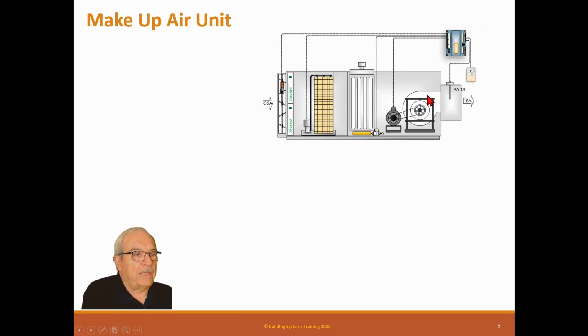Now this is a simple makeup air unit. This would be used for a kitchen or any other space where you have a whole bunch of air exiting the building for whatever reason. So the normal system doesn't have air conditioning because of that high temperature ambient condition. They don't have heat exchangers either. Normally, anywhere but the deep south, they will have an air washer in here which, using evaporation, is able to drop the temperature of the air, and that becomes the cooling cycle. And then we have a gas furnace in this one which will provide the heating to the space.